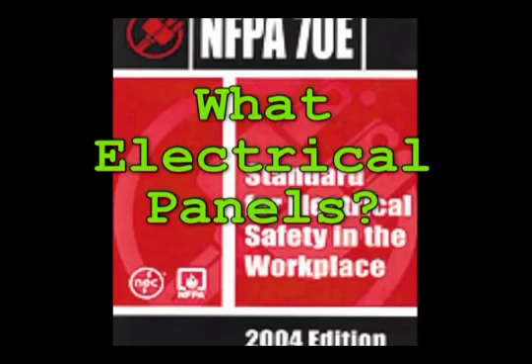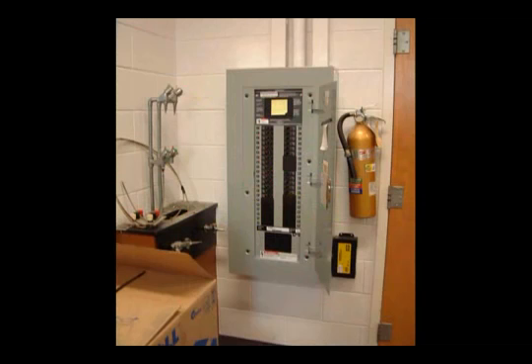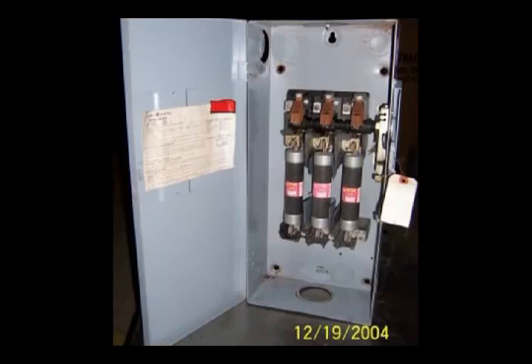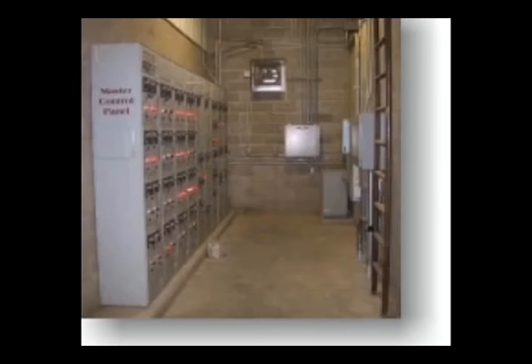Section 110.16 says that all switchboards, panel boards, industrial control panels, and motor control centers that are in other than dwelling occupancies, and are likely to require examination, adjustment, servicing, or maintenance while energized shall be field marked to warn qualified persons of potential arc flash hazards. The markings shall be located so as to clearly be visible to qualified persons before examination, adjustment, servicing, or maintenance of the equipment.